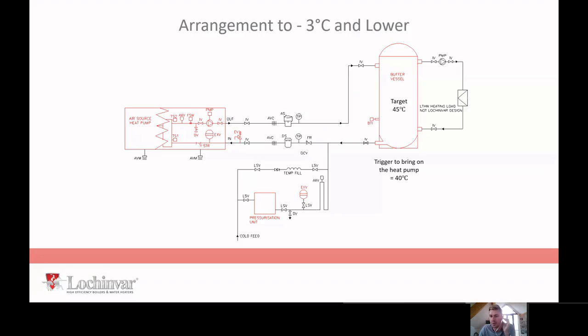So when we take a heat pump and apply it to a heating system, we have the air source heat pump, thermal store, and then ancillaries. Very important. Every single item of that is important and will pretty much always be the case. So what happens is your air source heat pump monitors a sensor, and that sensor's inside a thermal store. When you've worked with heating systems in the past, you've probably had a boiler with a low loss header. We have to have a thermal store with heat pumps because they work very differently.